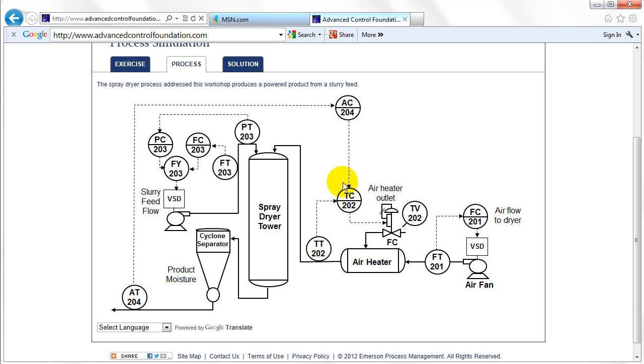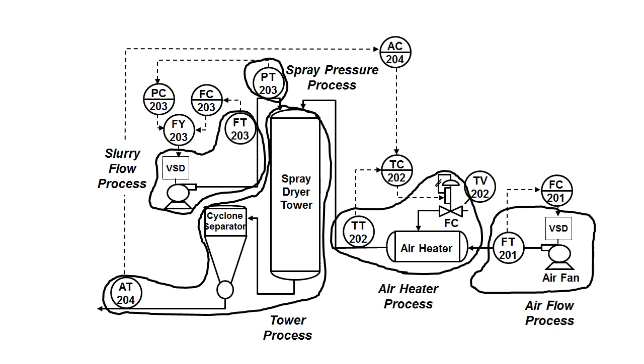Through automatic control, we're adjusting the temperature of the air supply to the spray dryer to maintain a product concentration that we would like to have. The feed rate to the spray dryer is critical. As the nozzles start to plug, the pressure goes up for a constant feed rate. If the pressure gets too high, then this should override the feed to the unit to keep the spray from being too fine. And so this is the typical type of control strategy.